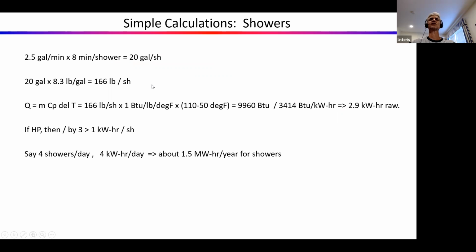You can do simple calculations, showing the tools at our disposal to figure out what's going on so we know what to do. Showers: you put a bucket under it, measure the flow, figure people usually take about 8 minutes a shower, except the kids, after I've yelled at them long enough they usually get out after that, that's 20 gallons per shower. That's about 2.5 kilowatt hours of raw energy needed in the water. With a heat pump water heater with a coefficient of performance of about 3, getting that hot water requires about a kilowatt hour per shower. Four showers a day means about 4 kilowatt hours a day, something like that.